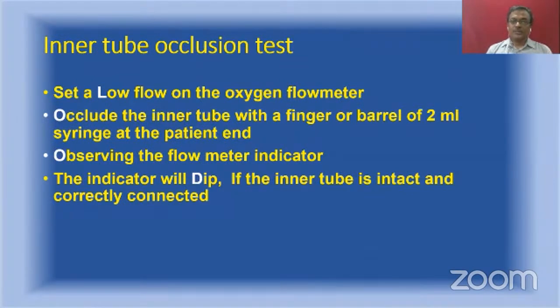So here you set a very low flow on the oxygen flow meter, 0.5 or 1 liter. Second step is to occlude the inner tube at the patient end with a finger, or better, you use the barrel of a 2 ml syringe. The third step is you observe the flow meter indicator, and if there is no leak in the inner tube, the indicator will dip, and you can say that the inner tube is intact. This is called inner tube occlusion test.